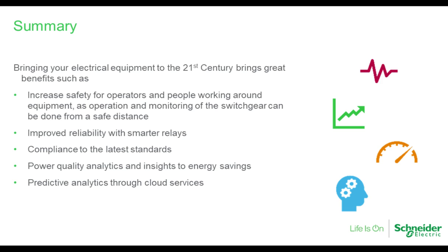We can also look at the power quality and insight to energy savings. This is one of the areas that we see a lot of people with either peak demand problems or poor power factor problems, or even harmonic issues where we can help out with power quality and manage those items and reduce them for cost savings, because harmonics increase a lot of heating that goes on in systems, and it also damages other pieces of equipment. So we can look at that through power quality and analytics of that.